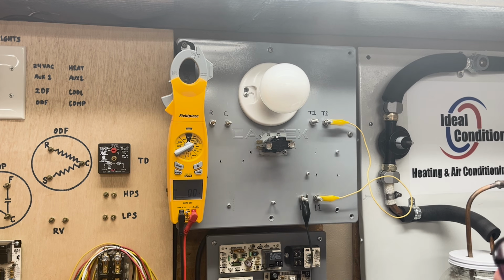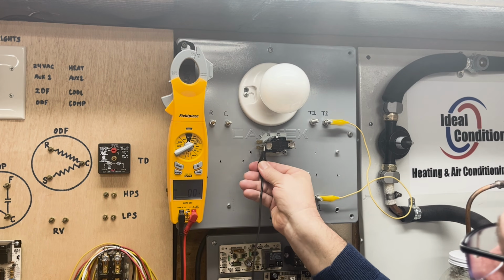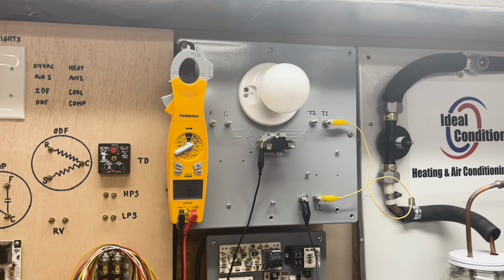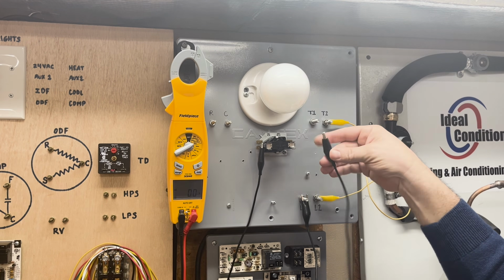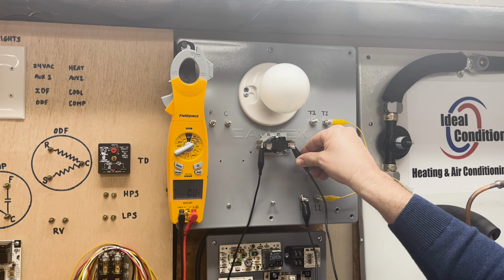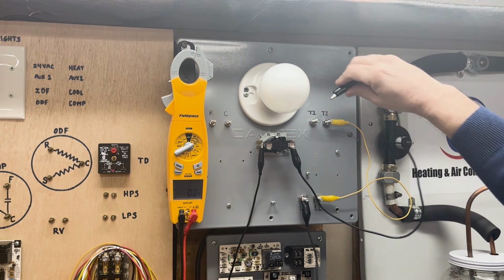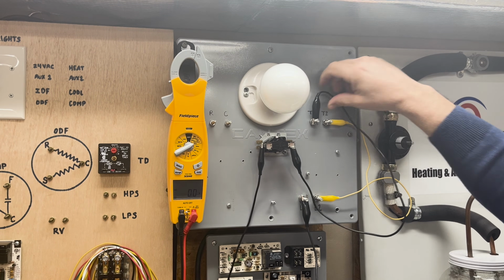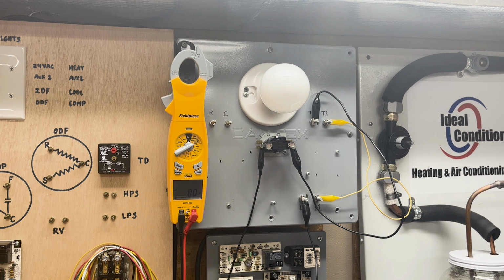So here's L1. We'll come over to our first pole. We'll come out of our first pole. And come up to T1. And that's all we have to do on the high voltage side. And we're going to apply 24 volts to this.